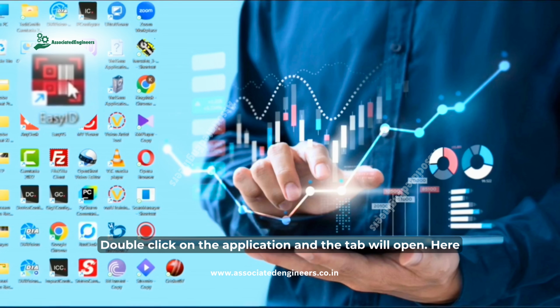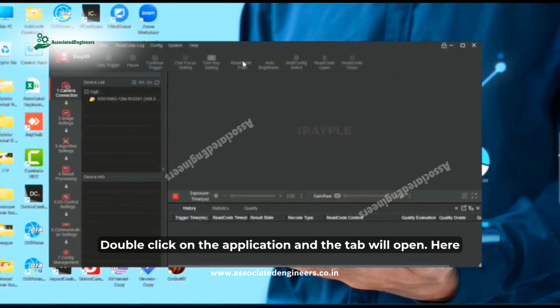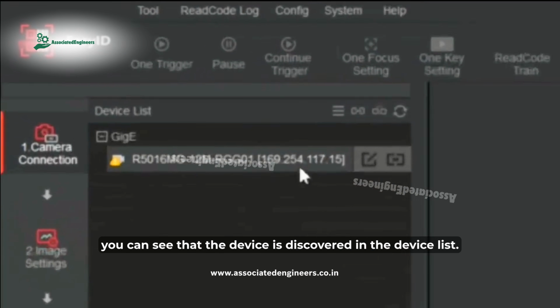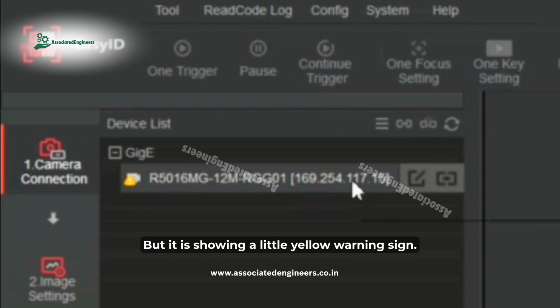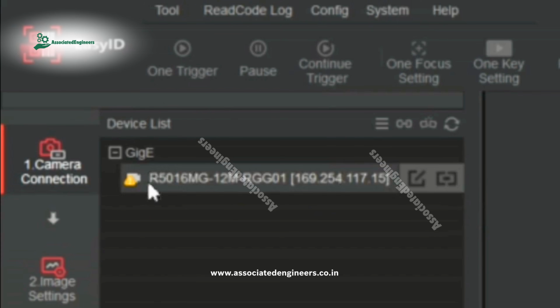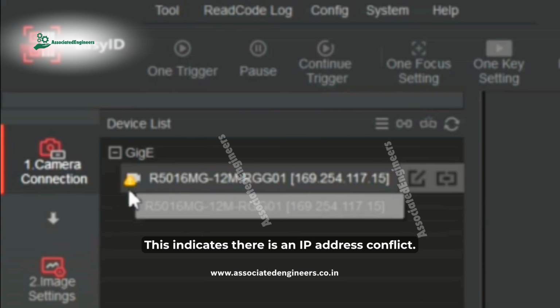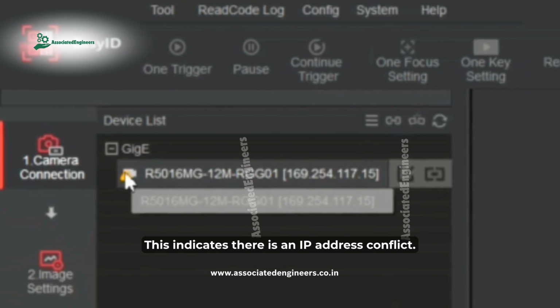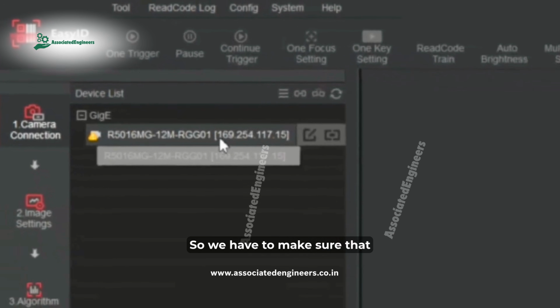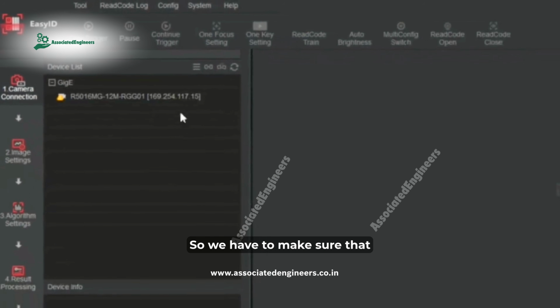Double click on the application and the tab will open. Here you can see that the device is discovered in the device list, but it is showing a little yellow warning sign. This indicates there is an IP address conflict. So we have to make sure that the port is in persistent IP.